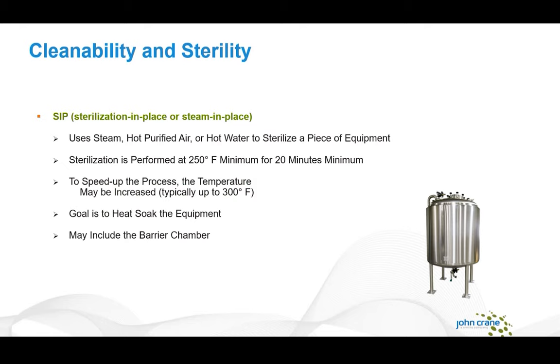We also consider sterilization in place (SIP) using hot steam or purified air. We understand there is a significant temperature involved — up to 300°F — and that this can last up to 20 minutes, so we design our seals to accommodate that full operational envelope.